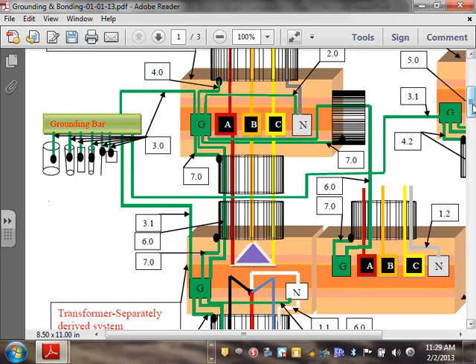You tie it on this side. Okay, now the flex also has to be bonded. The flex, both sides have to be bonded. Now the one that's going to, that one and that one, this could be a bushing, an equipment grounding bushing. It could be a wedge. It could be a clamp. It could be the fittings. The challenge becomes more strict if you guys are using 480-277, which it is. So you have to have some type of fittings that are more robust than the one that we use in 120/208. I'll show you a couple of examples when we go into the details.